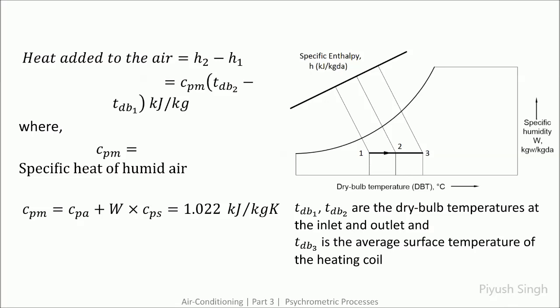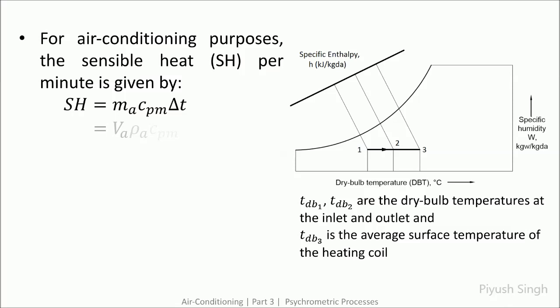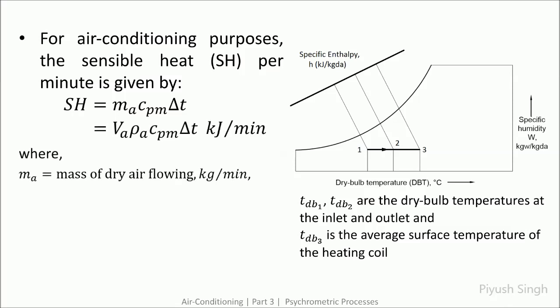The total heat added to the system is the difference in enthalpy between the outlet and the inlet, which is equal to the specific heat multiplied by change in temperature. CPM is the specific heat of moist air per unit mass, usually taken to be 1.022 kJ per kg·K. Here is an expression for the sensible heat added per minute.